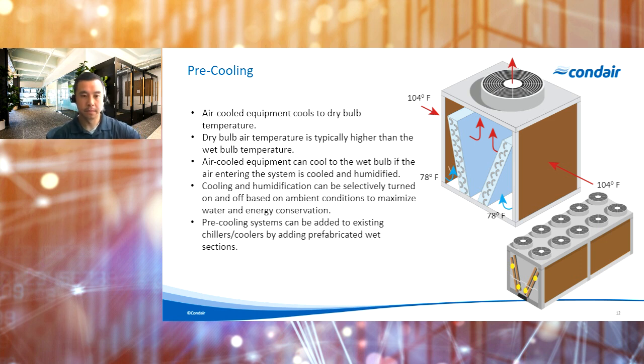So in these types of systems, the air used to cool equipment can be lowered to a value close to the wet bulb temperature of the air. Lowering the temperature of the cooling air can allow for the mechanical equipment to either be sized smaller or operate at lower levels, decreasing power consumption.